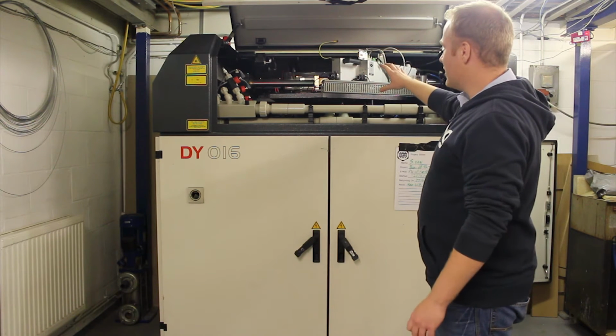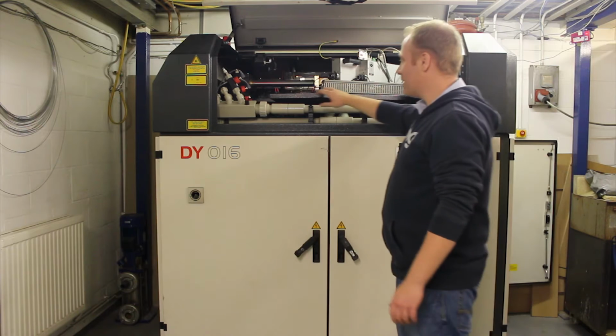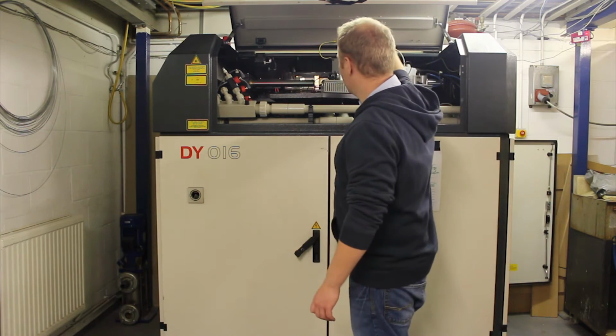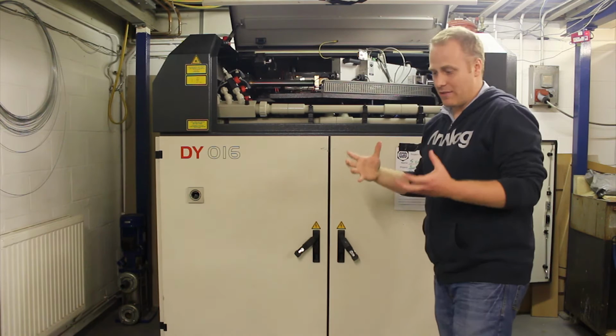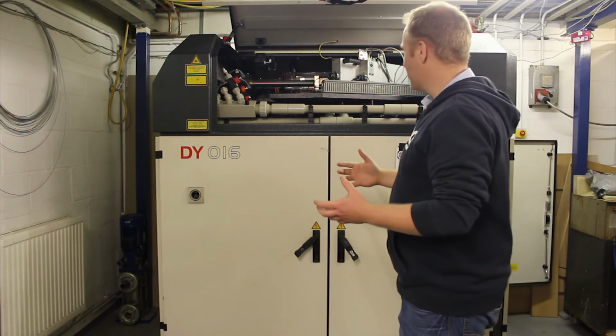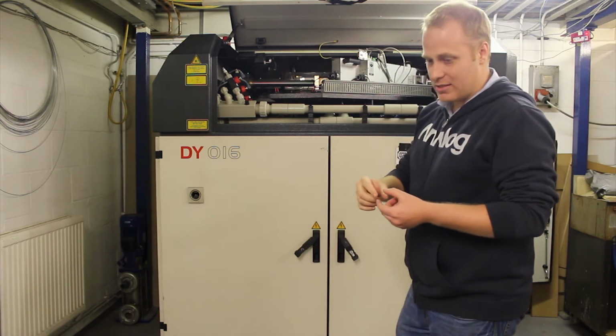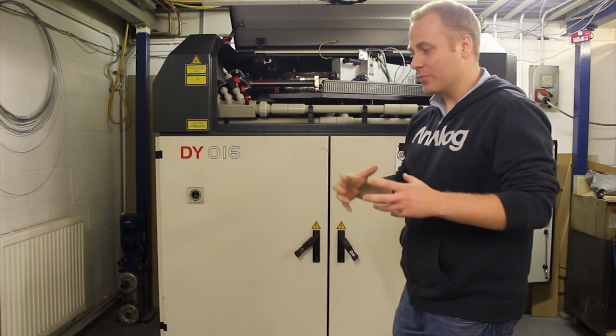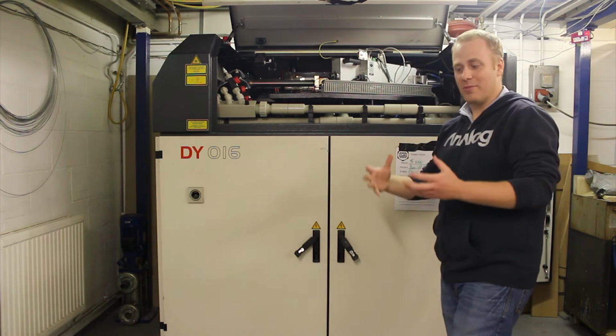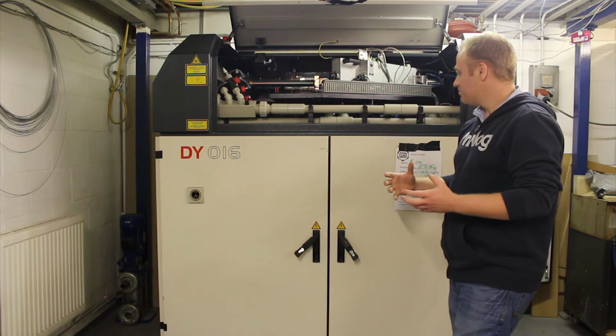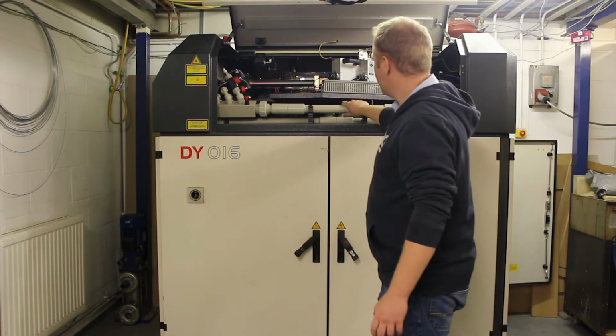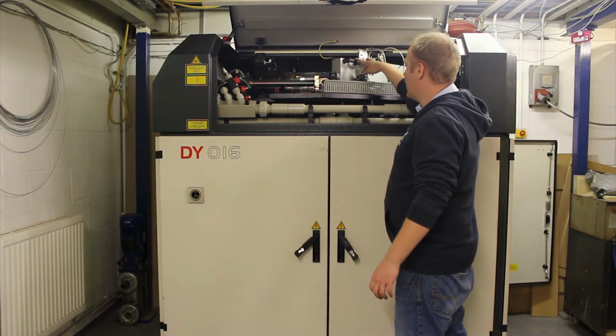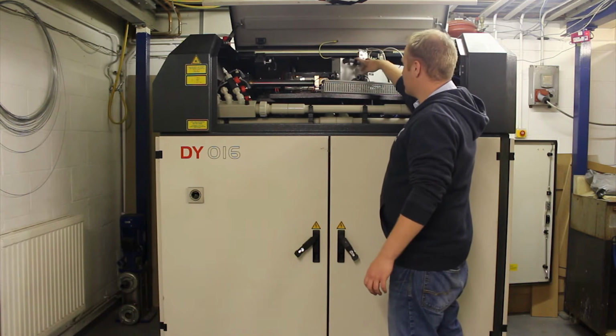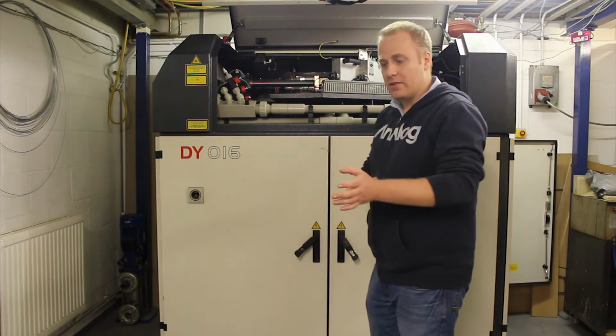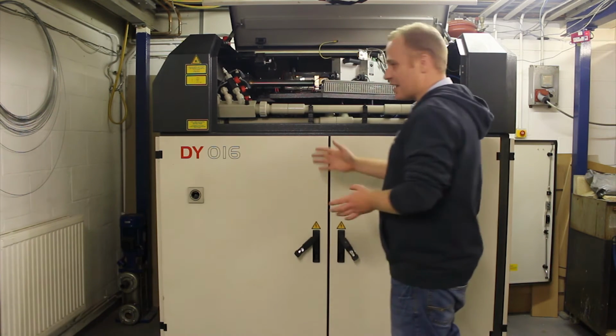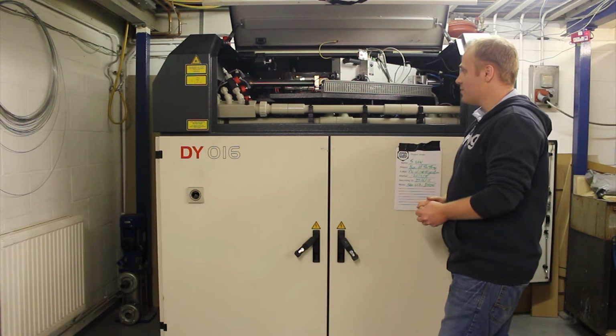Up top you've got the optics cavity, with a shock-mounted beam deck with 3 pump chambers, each with a 500 watt capacity. Inside that chamber is a YAG rod, pumped with luminous flux from diode bars. You see there's a lot of plumbing inside it, and 2 fiber launches here. This is where the light is directed down one of the 2 fibers, and you can have different proportions of light going down each fiber to do different jobs.